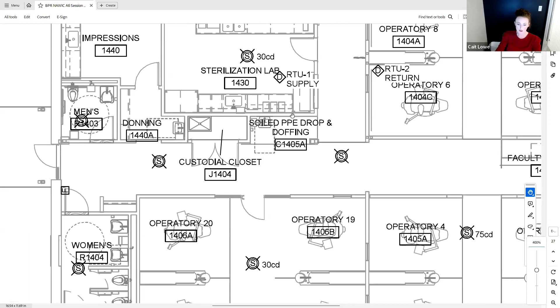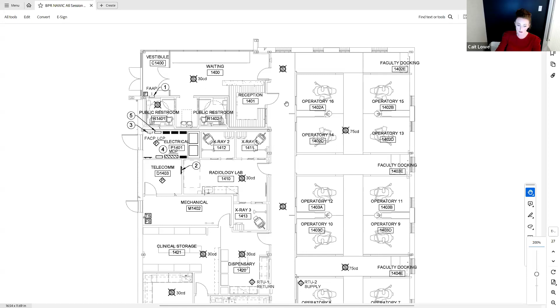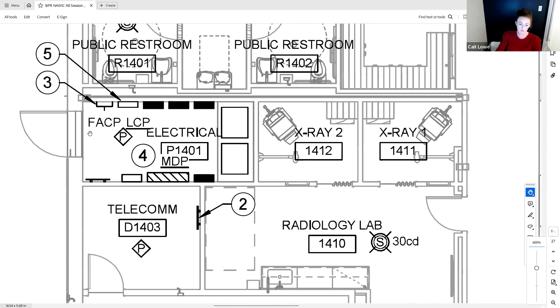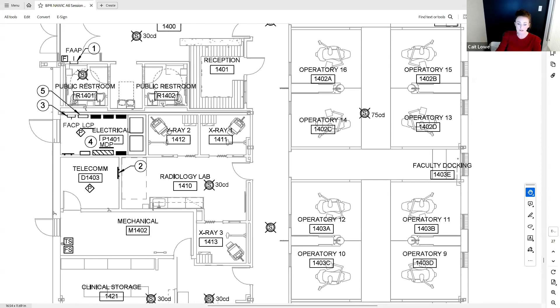Same thing here, we've got some sensors for the fire alarm. You're going to do your fire alarm, and the contractor's going to pick all of this up, but electrically, here's the nugget, guys. Here's your electrical panel, here's your fire alarm panel, lighting panel. But who runs all the conduit? We do. The fire alarm guy is just providing that itty bitty little wire, and don't let him tell you he needs a 3/4 inch, because he does not.